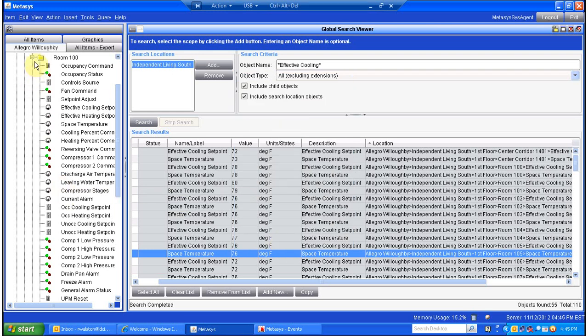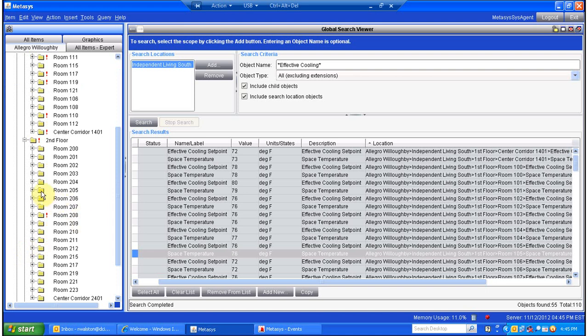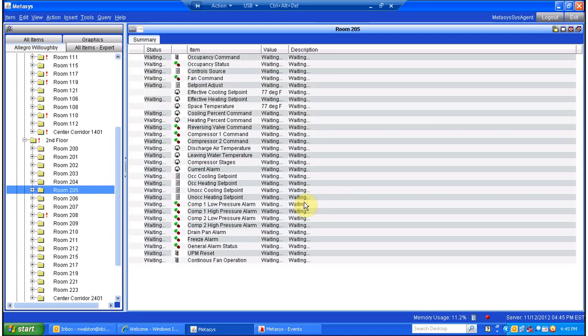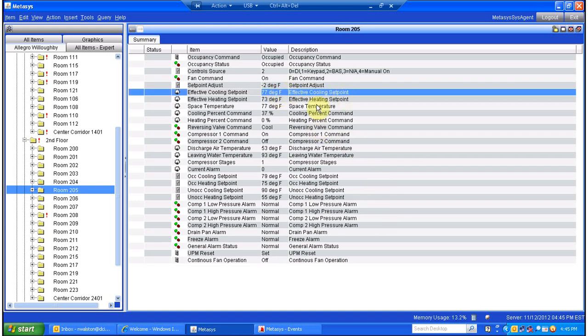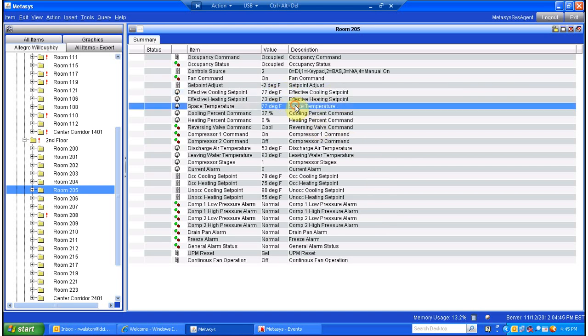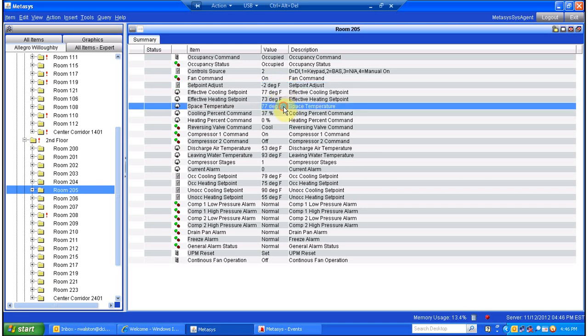Now we're going to look at something else real quick, because on the second floor, room 205 just called and told me they were hot, so I'm going to look over here. Their effective cooling set point is 77 and their space temperature is 77. And their adjustment is down two degrees — they are cooling to where they should be.